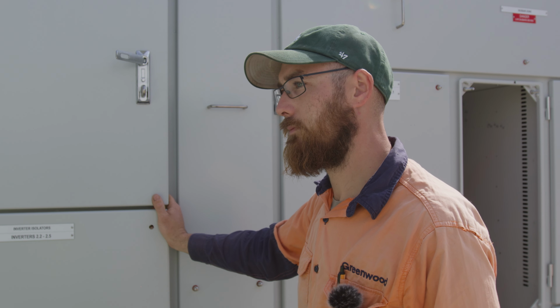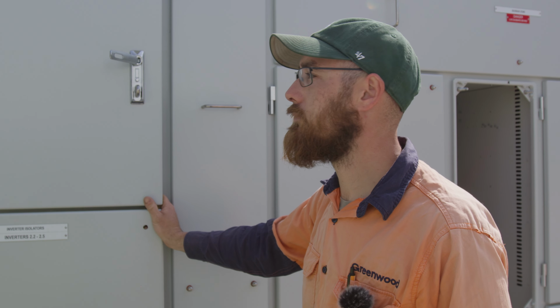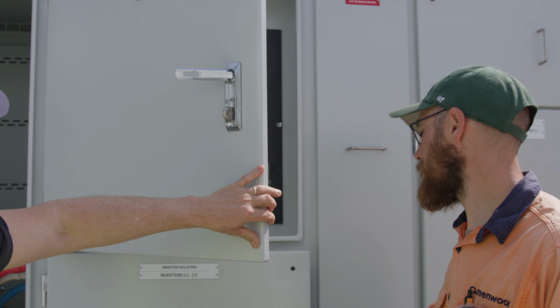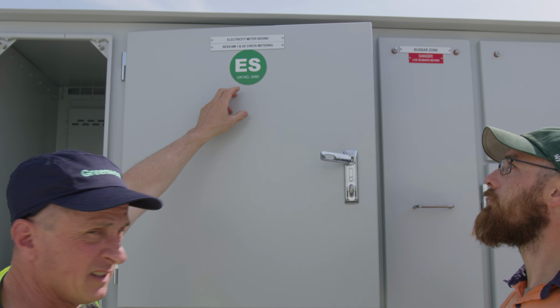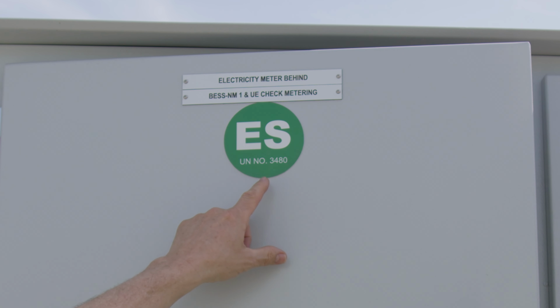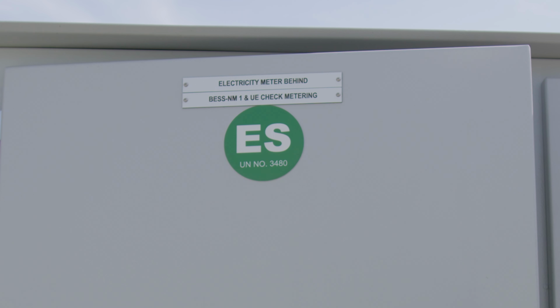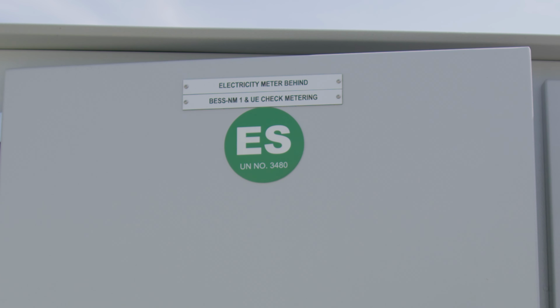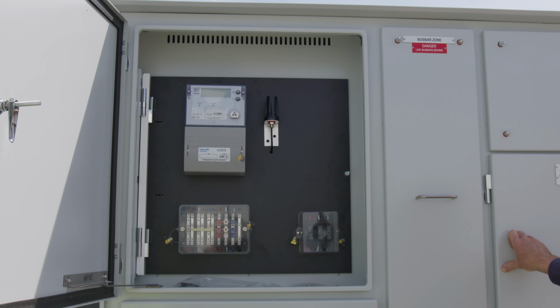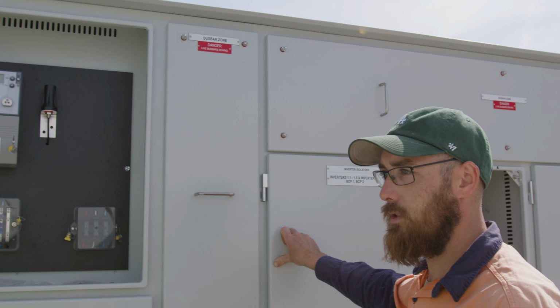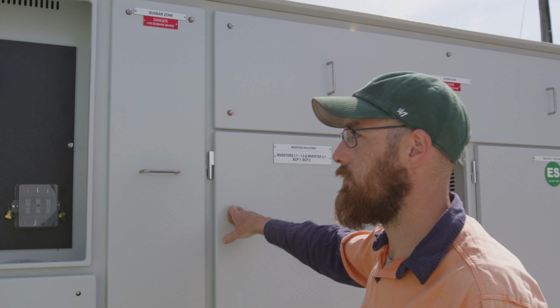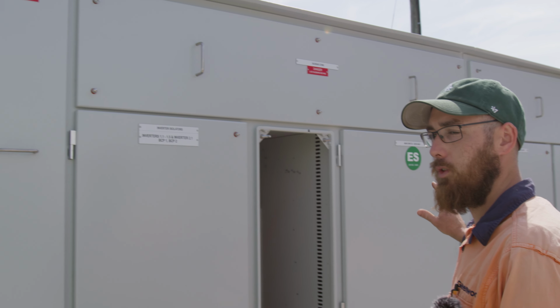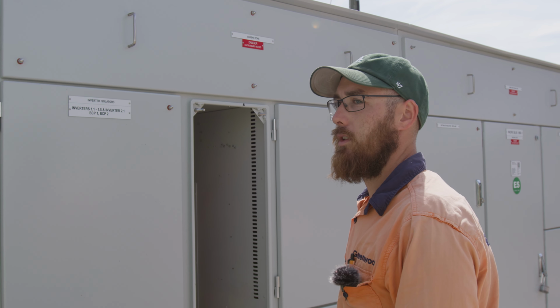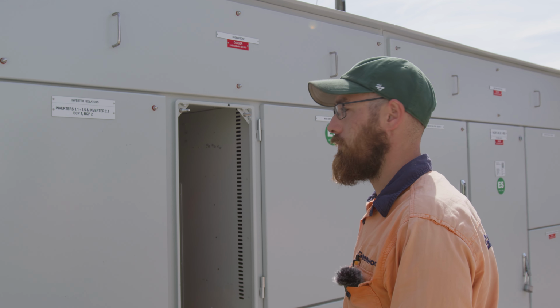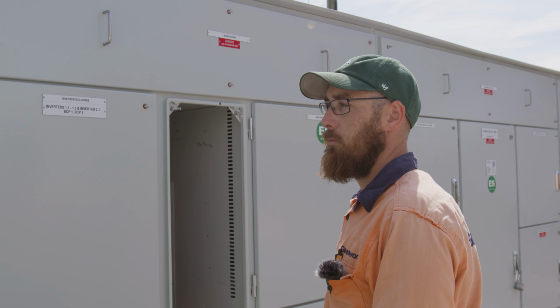Wow. Okay, moving on to the section up here which is the meter, and you can see the signage here, energy storage, and there's a UN number, and that number 3480 correlates with the kind of battery storage chemistry that's being used on this site. This is one of the 2 NMIs that are on site. So the mains cable will be unmetered until it reaches this board, and from this board we have 2 separate NMIs. This is one of them. So this one is the meter for a 2500 amp main switch.